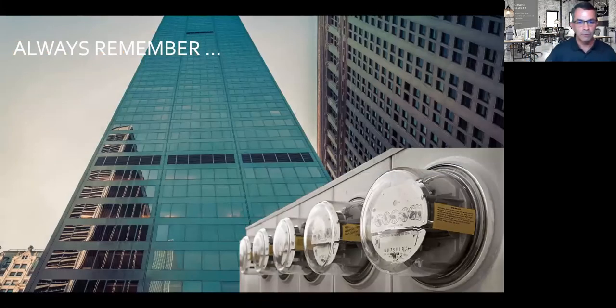So we need to make sure that we keep our attention and focus on the fact that the building owner pays for the system energy. You'll do your customers a great disservice if you allow anyone to convince them to just look at the chiller or a single component. Many owners have complicated systems in their building and use submeters on system components to provide data that tells them how their system is operating and maybe where to focus their time and effort to be in a continuous commissioning mode. However, always remember that the utility meter is on the building, and it's the building or the system that counts.